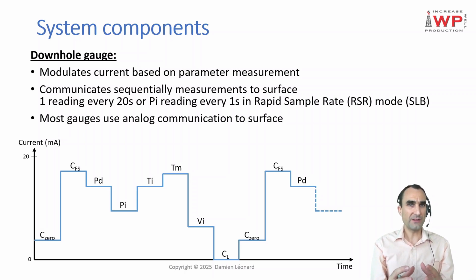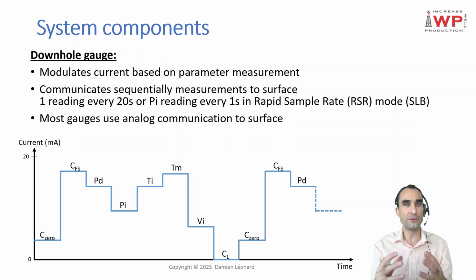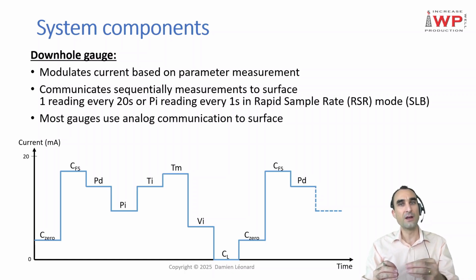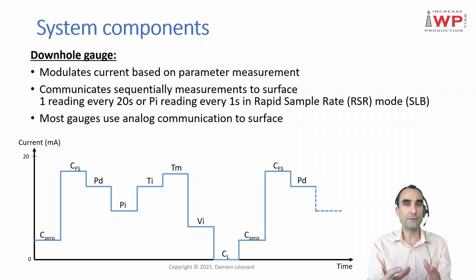Now for Schlumberger in the past, I don't know if that's still the case, but they had some downhole gauges which were not ESP gauges that were using digital communication, and I know that some ESP manufacturers only use digital communication for their gauges. For instance, that's the case of Oil Dynamics and Leva. They communicate with their gauge using digital mode. So just to briefly talk about it, again, I have a dedicated video about digital gauges and the difference with analog gauges later on. But basically for the digital gauges, the communication with the gauge is coded at the gauge level and it's sent back to the surface by data pack. And so the surface panel needs to receive several of these data packs to then have a full reading. So because it is a different communication mode than the analog gauge, the frequency of data updates is going to be different than with analog gauges.